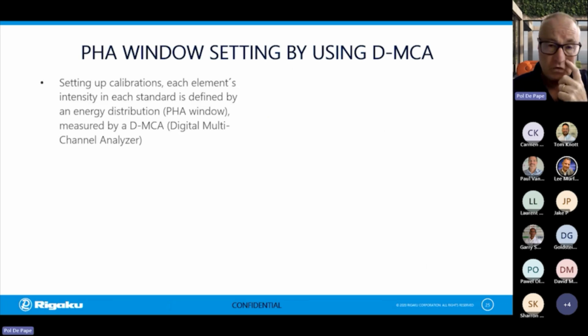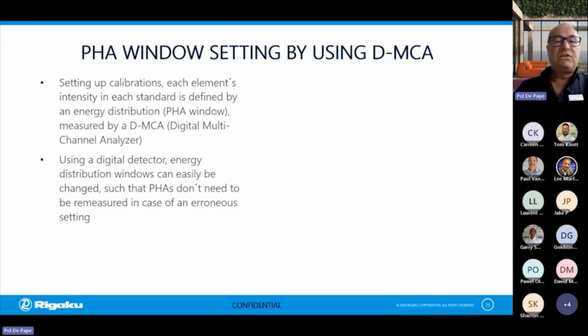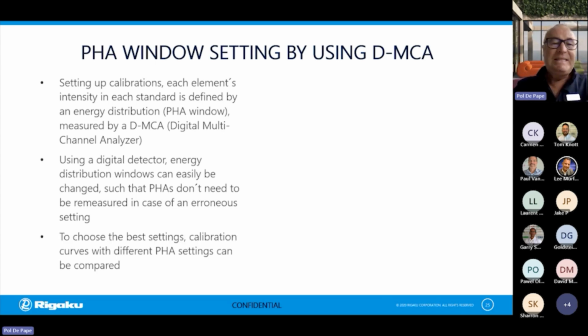The PHA window is, of course, something important. It's the pulse height analysis window. It's an energy distribution, and this is using this DMCA, this digital detector, so energy distribution windows can easily be changed. As we are analyzing all the energies at the same time, we have all the energies within one window. So we can easily change the settings of that window. People who have already done this may understand that it is a big advantage instead of having to re-measure each PHA again after having changed the parameter. This is not necessary anymore.